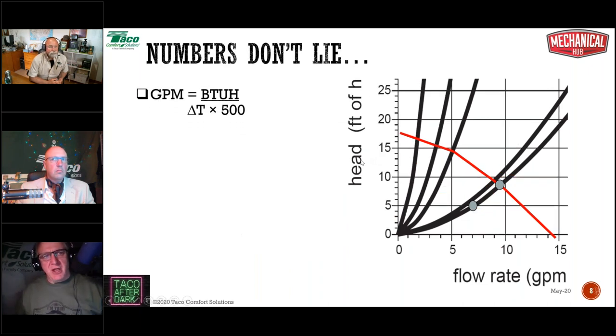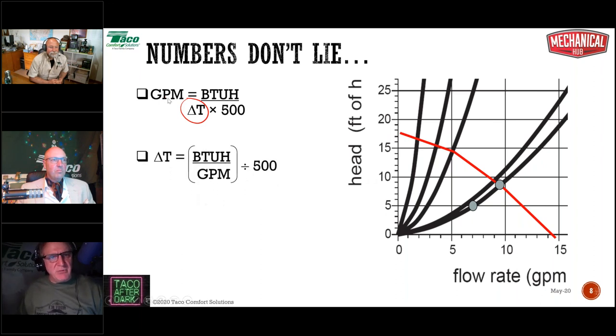However, numbers don't lie. Now remember, GPM equals BTUH divided by delta T times 500. That's the universal hydronics formula. It's also algebra. Remember that algebra you took back in sixth, seventh grade, and you're thinking, this is garbage, I'm never gonna use this in the real world? Today's the day. We can isolate for delta T. We simply do a little algebraic manipulation and we find that delta T equals BTUH divided by the GPM you were using to deliver the BTUH, divided by 500. We do that math and we can find out what the delta T would be under this situation.